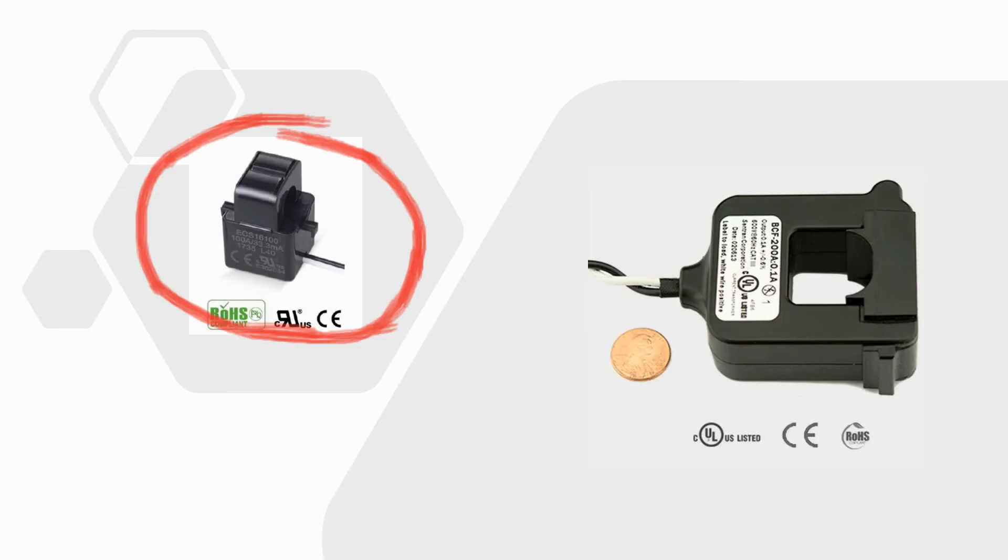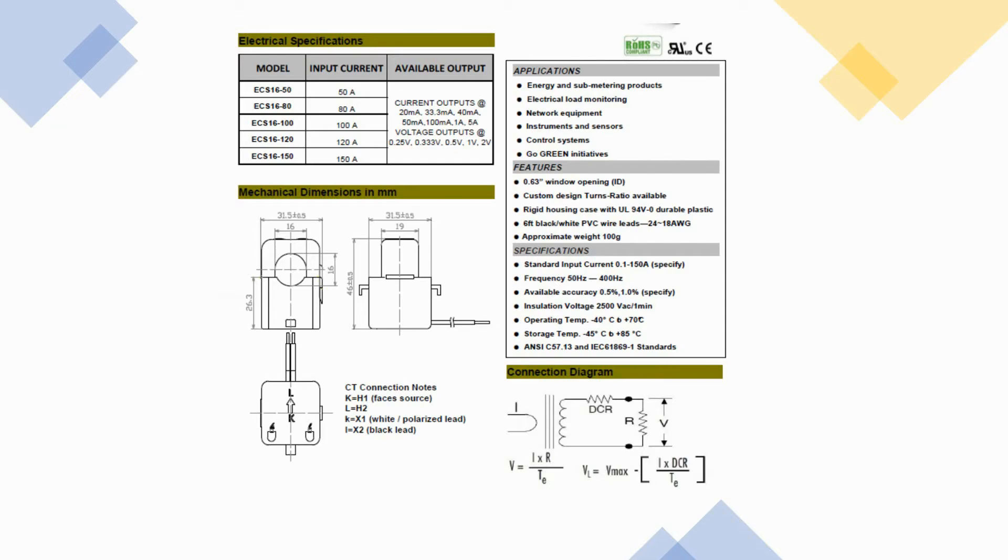Qualitrol provides two types of split-core CTs for AC current measurement. Both come with 15 feet 2-wire pigtail. The CTs provided for measuring phase currents have 0.5% accuracy, whereas the CTs provided for heaters and motor currents have 1% accuracy.